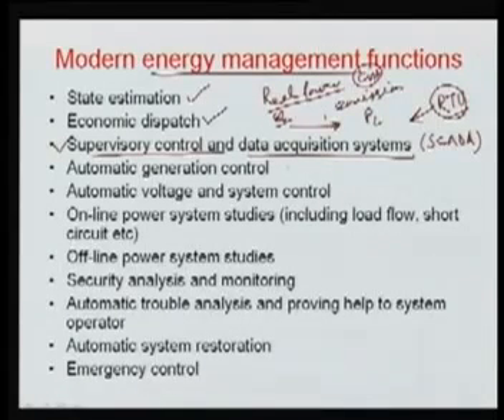Another function is called AGC, automatic generation control. It is also known as load frequency control. It is sometimes called primary, secondary and tertiary control of the generating units, and we will see automatic generation control in much more detail in later modules. Here we try to set the power generation of the generating units so that we can maintain the frequency of the power system. So this is your AGC.